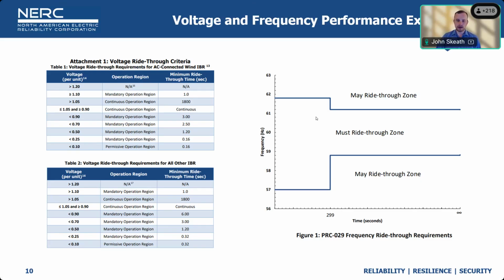On the right-hand side, you can see the frequency counterpart, and so it's a fairly square box. You have a 57 and a 61.6 that goes out to about 299, 300 seconds, so up to 300 seconds. And the other is an indefinite ride-through where, I forget the exact value here, and I would have to take a look at the standard, but I think that's 61.2 and 58.9 or really close to 59 hertz there, as those are to be a little bit beyond the expected over-frequency and under-frequency load shedding to ensure that there's a ride-through in that last little safety net, so that we're not shedding load in addition to also not expecting generation to go through. But those are the charts for the expected ride-through.